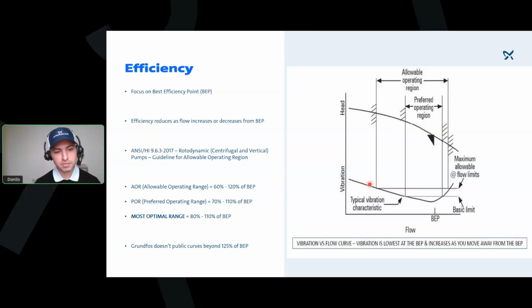But if you look at the downside curve, now we see a vibration curve. So you see that when you are here, this is the BEP, right? Your best efficiency point for this example, that's when you have your lowest vibration. And you see how once you're out of the preferred operating range, how quickly the vibration starts increasing, right? And you don't want that because the more vibration you have, the more energy consumption you're gonna have. So that's about efficiency.